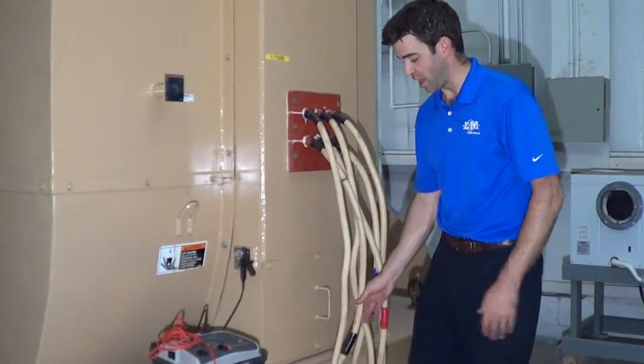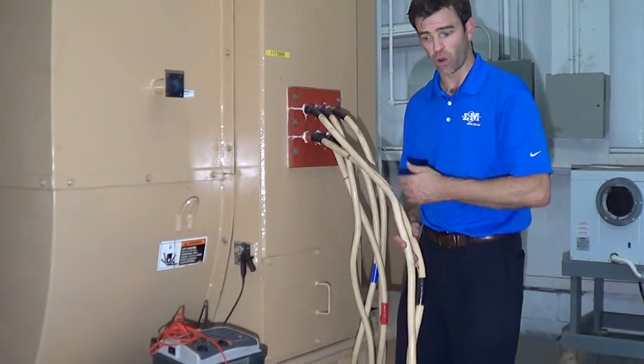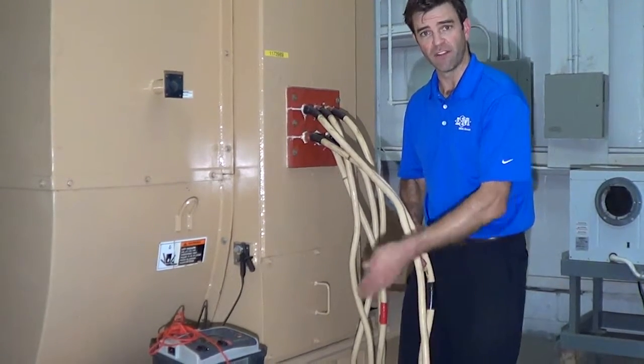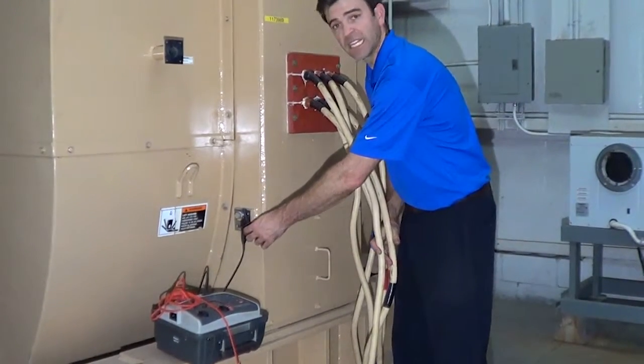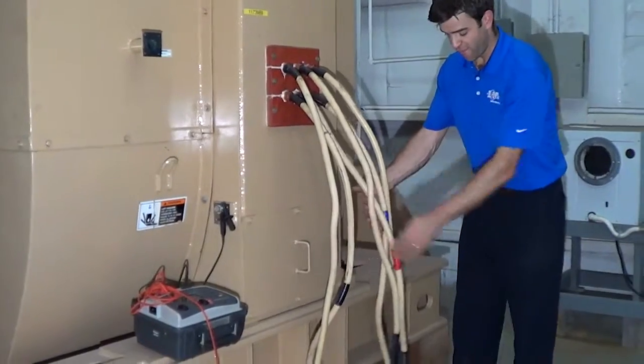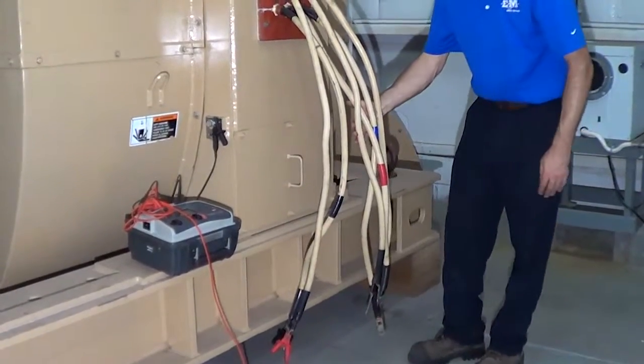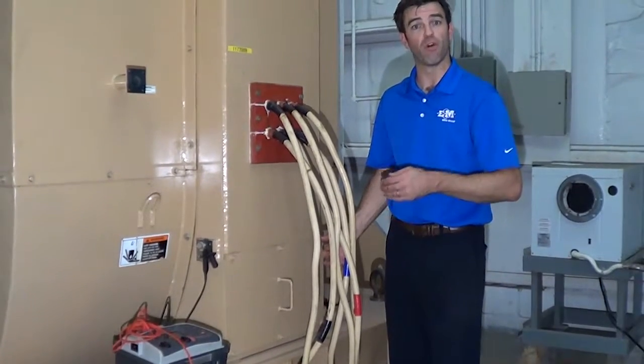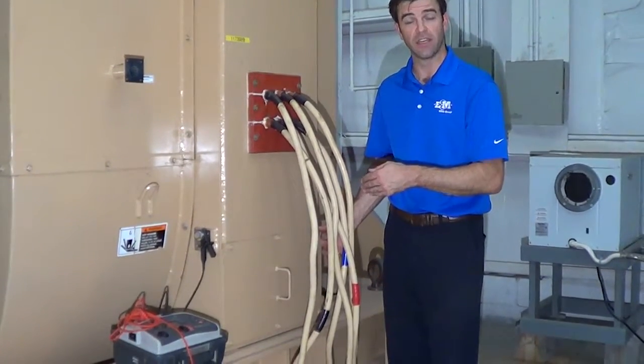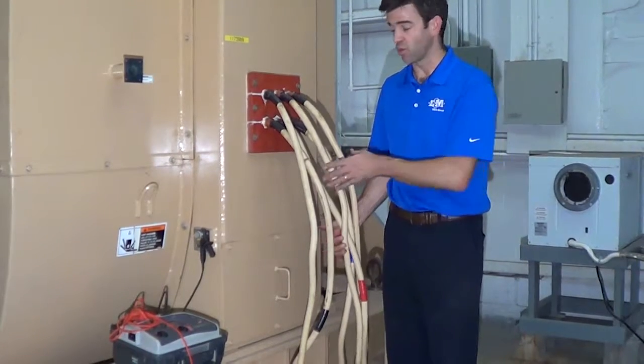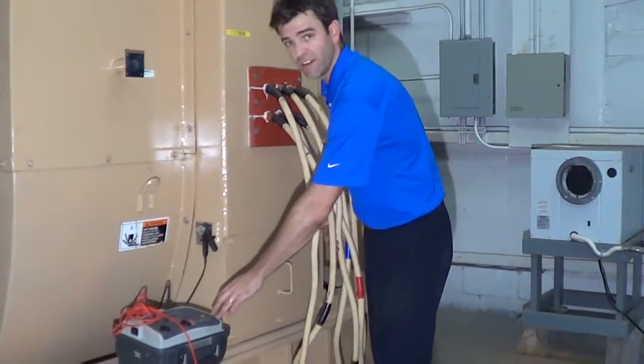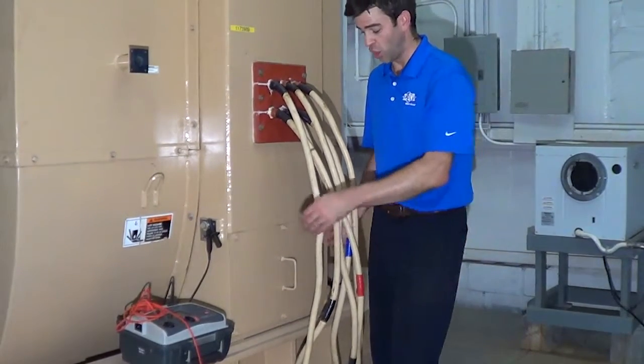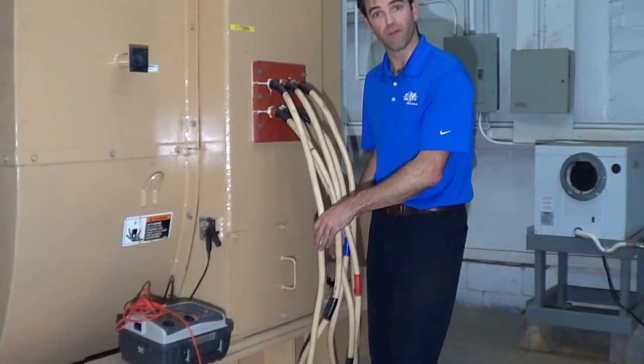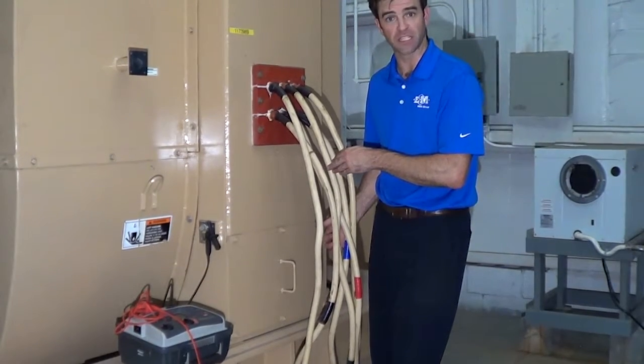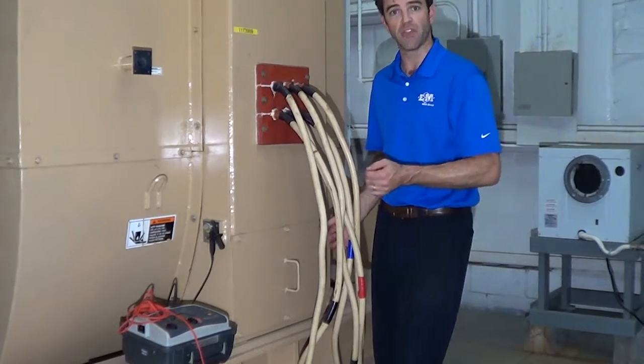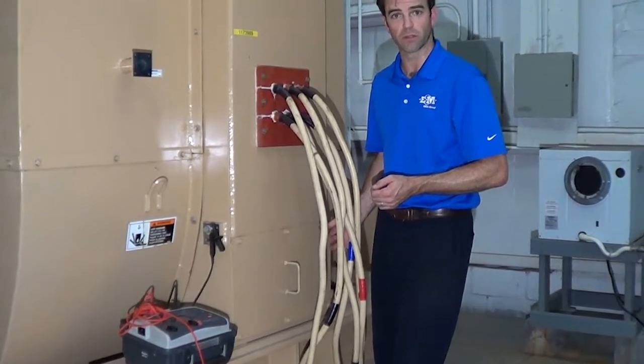Here we've got phase A, or leads 1 and 4, disconnected and connected to the red lead of an insulation resistance tester, and the black lead connected to a hard ground. Note that the other phases have been connected to ground using a bare copper wire. This is critical to allow both a phase-to-phase and a phase-to-ground test to be completed simultaneously and also to render the other phases safe. Once the polarization index and insulation tests are completed, ground the phase you're working on with a bare copper wire before touching it, and then carry on to the other phases. Record both the insulation resistance and the polarization index test results in the field report.